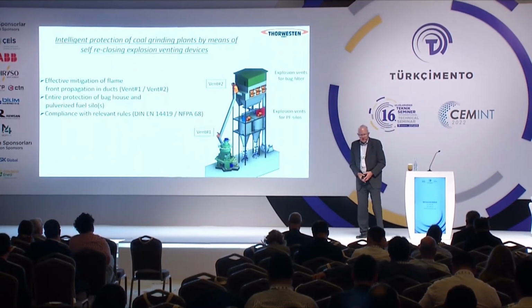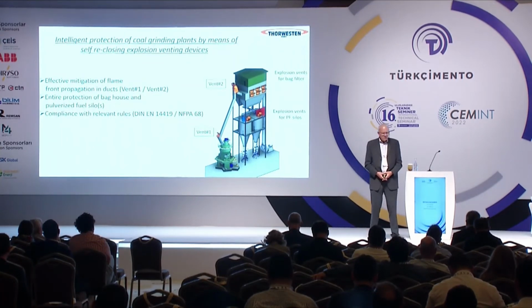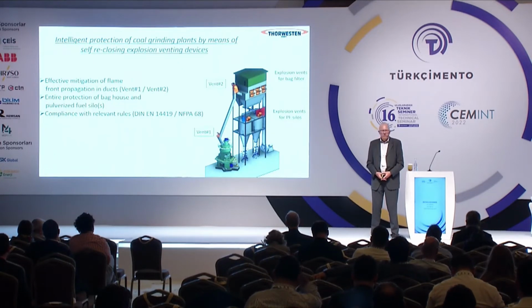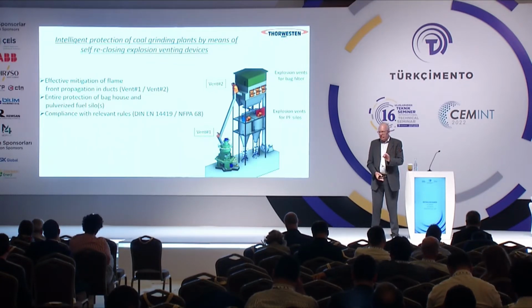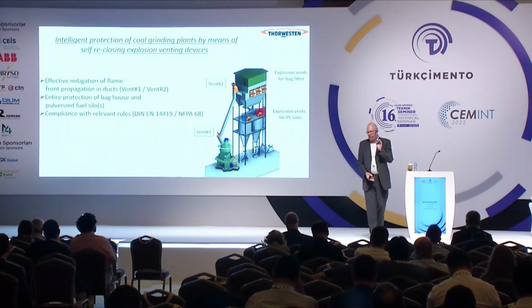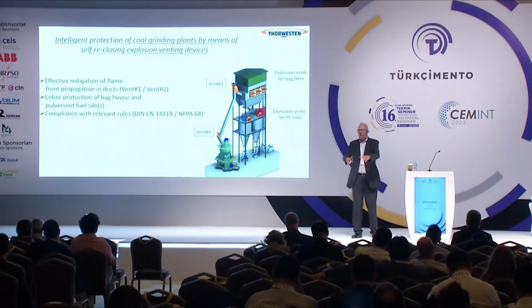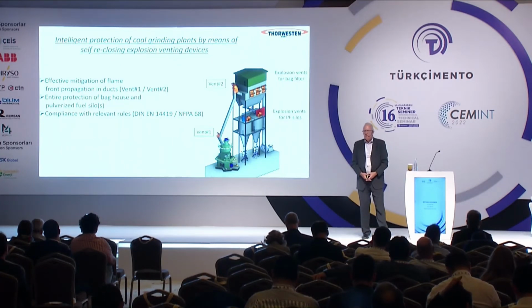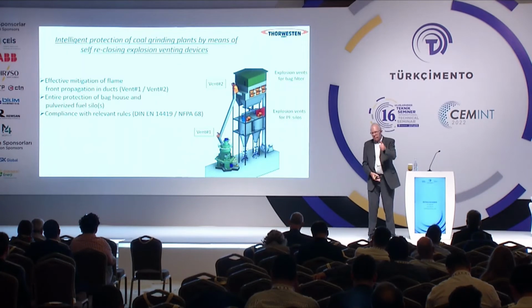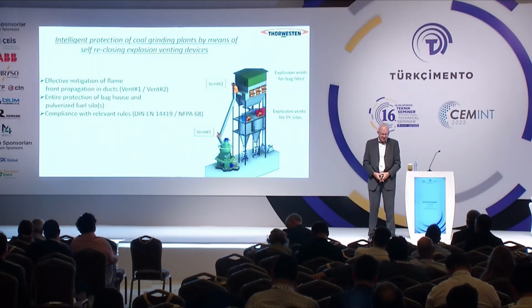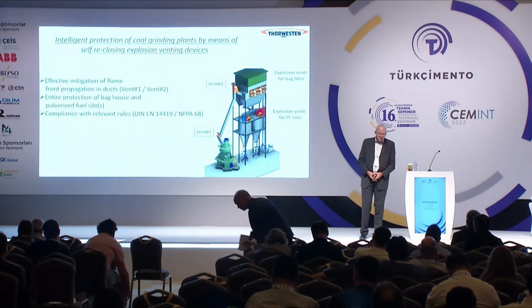Area number 3 is the pulverized coal silo. For this storage of coal, we are offering engineering for local manufacturing, and we are offering explosion venting devices designed in accordance with the needs. In most cases, and this is given by the rule, the venting area or the size of such a venting element is determined by the volume that needs to be vented, as well as by the characteristics of the coal. You may know these values, KST and Pmax. These are very decisive values in terms of the calculation.